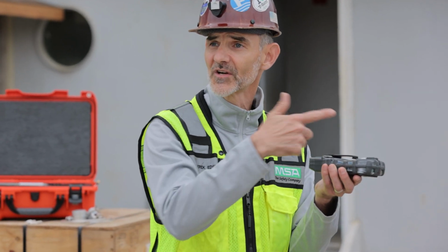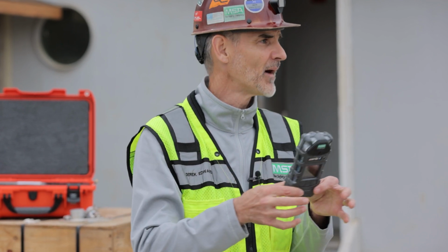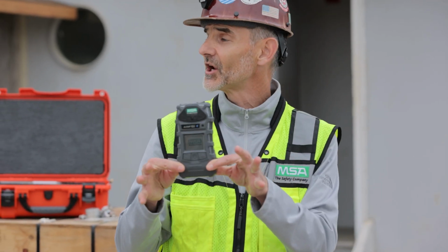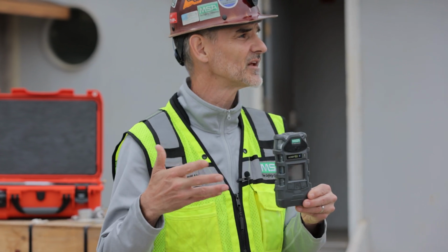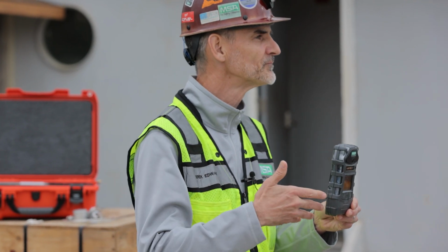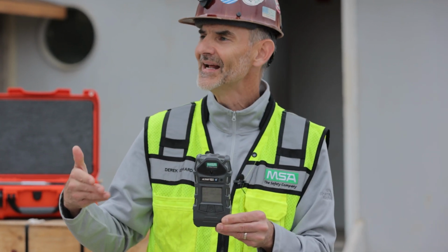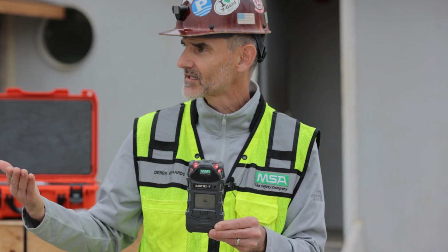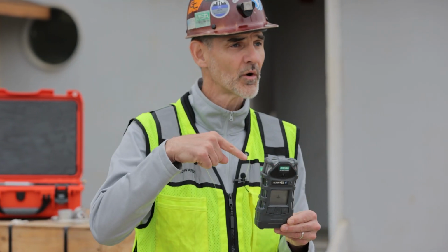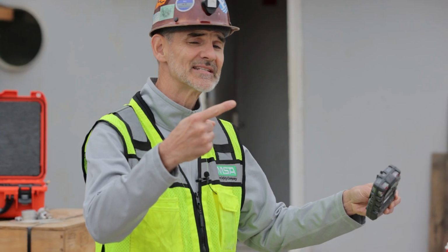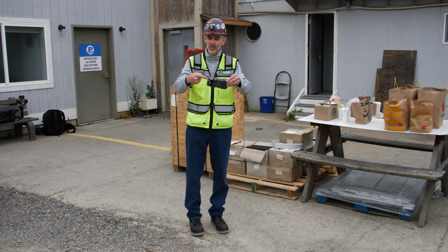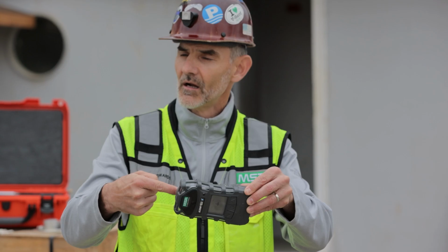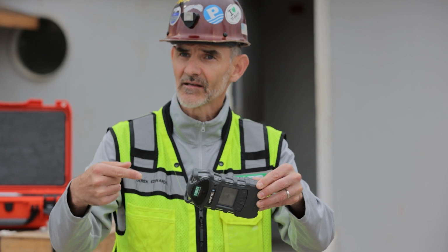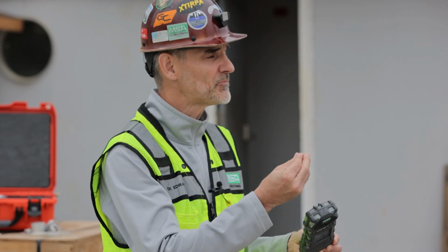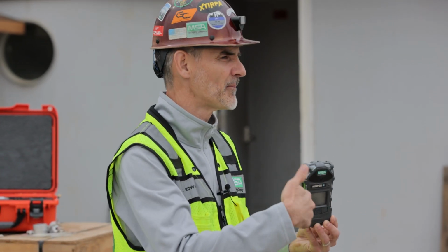Now the first thing that's going to happen that might alert you is that it's going to go into alarm, and you're probably going to think there's something wrong with the instrument. There's nothing wrong with the instrument. It's asking you to do a test. It's a pump test. So now we're in alarm. So now what we're going to do is we're going to take our finger and we're going to block the inlet. So it beeped 3 times and now it's going to go on about its business.